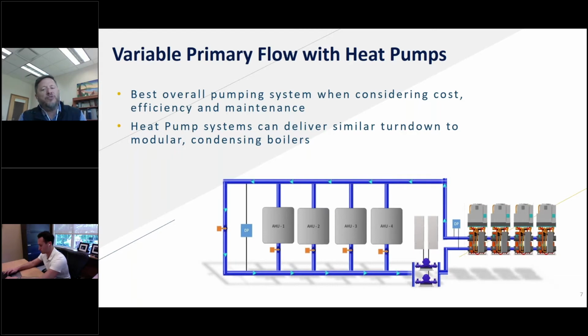And so when you design a system with all of the devices capable of operating in a variable flow application, it gives you the flexibility to make those decisions on a specific application basis. As I said, individual, larger packaged units are going to have some of the similar challenges to older boiler system setups, where you don't have as much flow turndown. But if we go to multiple smaller packaged units piped up together on the roof, or a modular array similar to modular boilers, you have the ability to not only match the capacity but match the flow, which at the end of the day is going to drive your most efficient system. Okay.